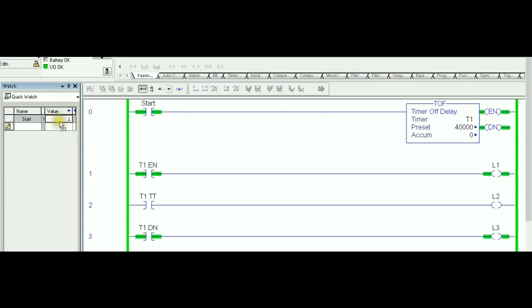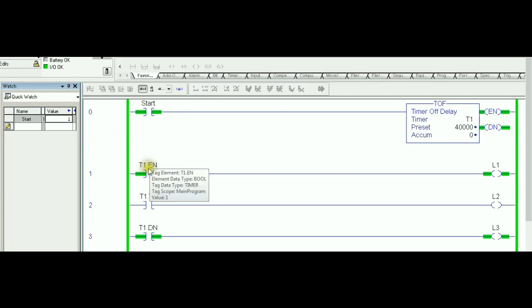Let's see what will happen once we trigger, push on the start button. You see right now to the left it's closed, it's reading one from the PLC memory. The XIC is true, logic continuity across the rung. And what happens right now? The TOF actually resets. So point number two: to reset the TOF you need to enable the rung.